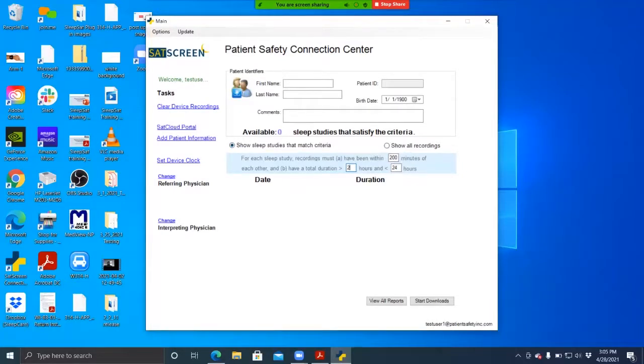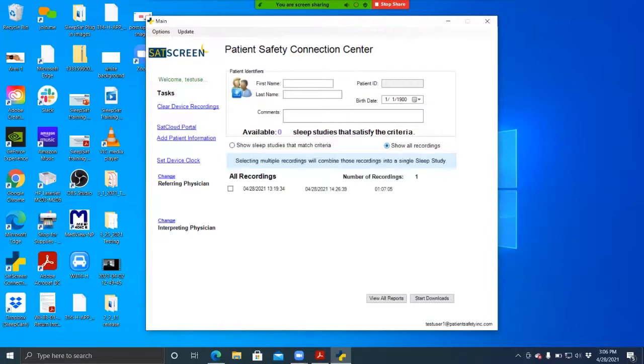These criteria are for each sleep study, recordings must have been within 200 minutes of each other and have a total duration between 2 hours and 24 hours. As you just saw me do, this criteria section is editable. But in the situation that you don't see any report come up when the SleepSat finishes connecting, the first thing I'd recommend that you do is change this selection from show sleep studies that match criteria to show all recordings. As you can see, I have an hour-long recording on this device.